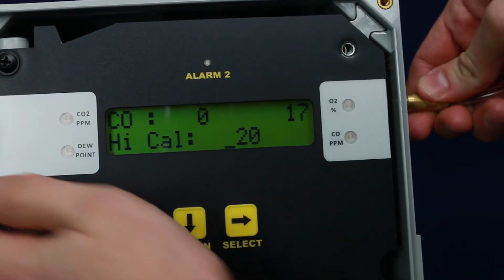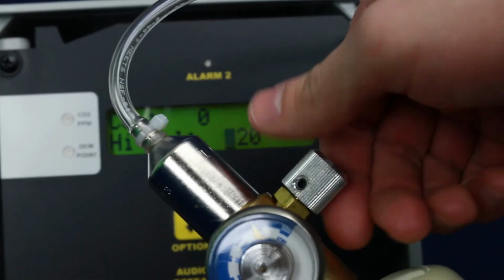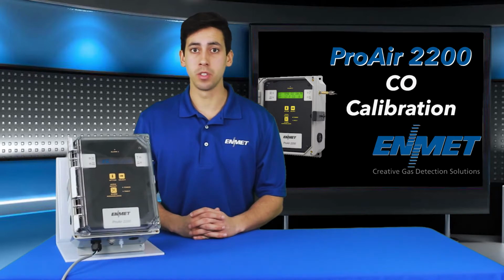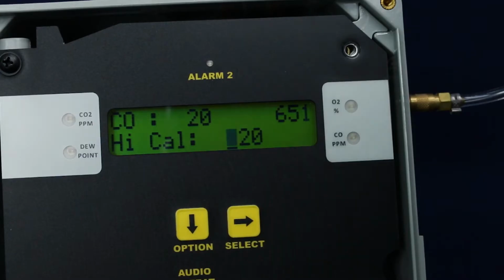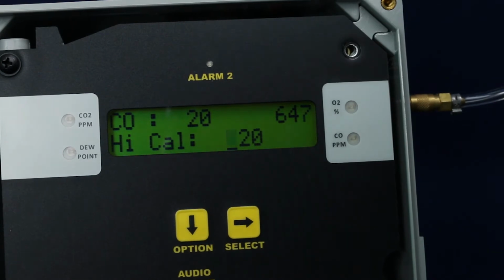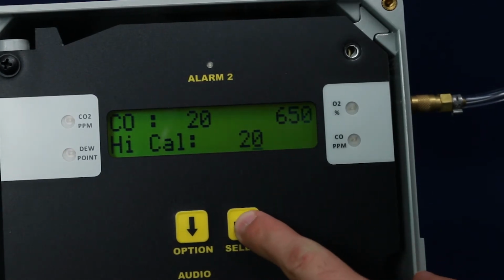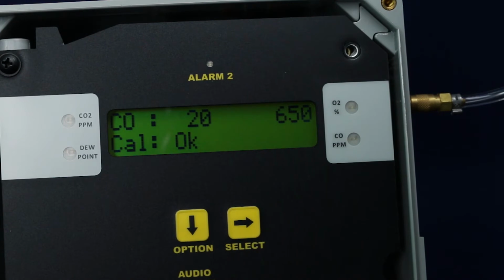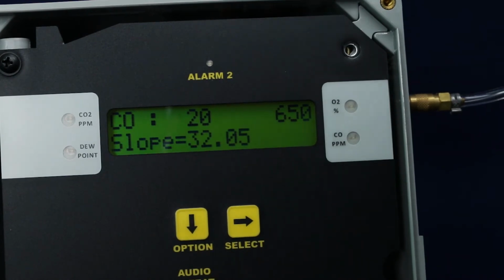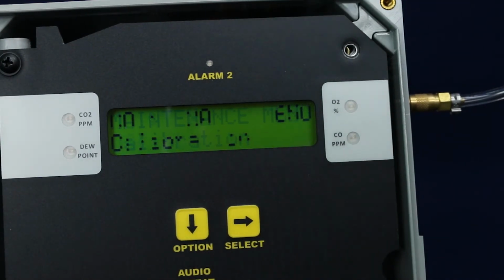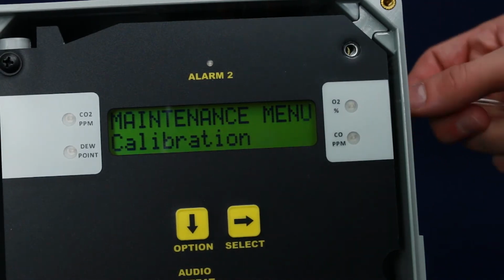You will see the signal on the upper right-hand side of the display rise with the present value on the upper left-hand side of the display. Once the signal stabilizes after about 2 minutes, you will accept the calibration. To accept the calibration, you will use the Select key to move the cursor over to the right until Cal OK is displayed.